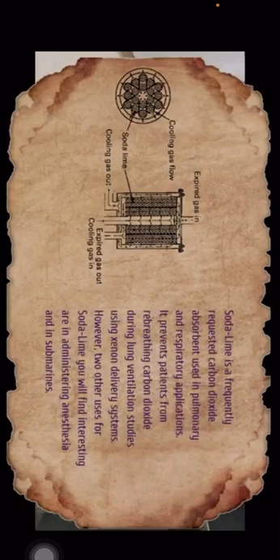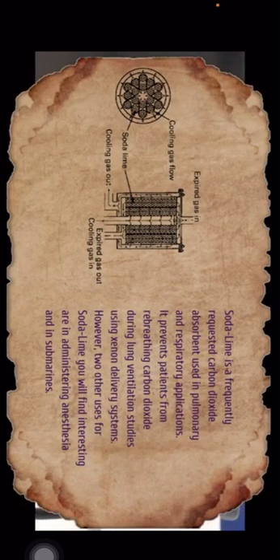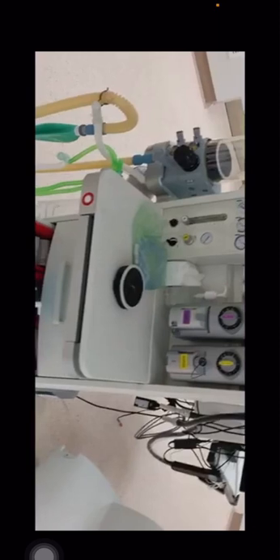The soda lime is a mixture of sodium hydroxide and calcium hydroxide used in granule form in enclosed environments such as the anesthesia machine, to absorb CO2 from breathing gases and prevent carbon dioxide retention.